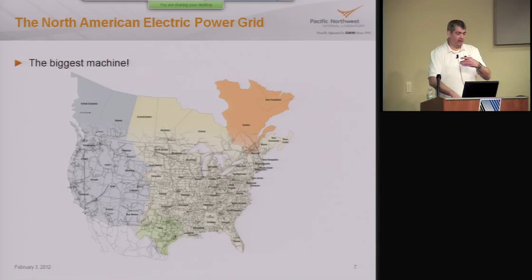Within each of these machines, utilities collectively work together in a common way to operate the systems. It is possible to push power between these grids, but to do that you have to convert from AC to DC to AC, because the Eastern Interconnection might be operating at 60.01 hertz while the Western Interconnection is at 59.99 hertz. You can't just close the circuit and move power there — there's not enough synchronous torque to pull them together, so they convert to DC to move across those grids. There are about half a dozen links between the East and West, 3 between Texas and the others, and some DC lines going from Quebec into the New York area.